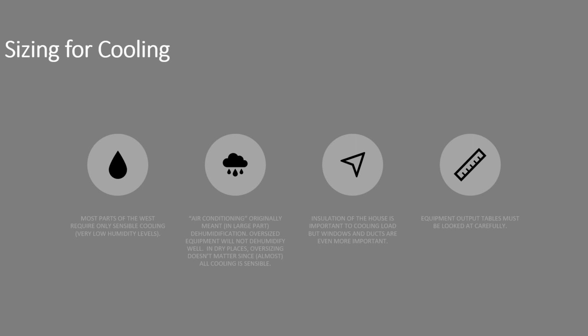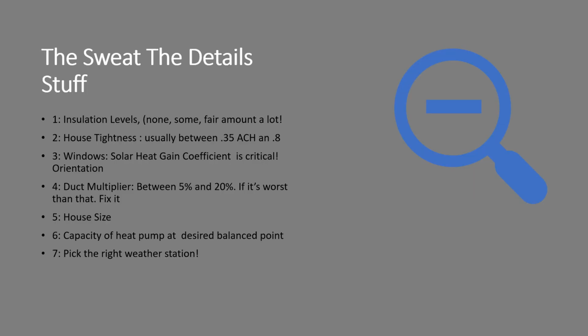And insulation of the house and good windows and good ductwork are probably the biggest factors that are going to influence the size of the heat pump that you put in. And I'm sorry, nobody likes to look at detailed capacity tables, but to pick the right system, especially for cooling, you really have to look at them. In summary, these are the items you sort of have to sweat the details a little bit on. Insulation levels, don't worry if it's an R33 or an R38. Doesn't matter that much, but none, some, or a fair amount sure matters in the ultimate size of the heat pump you put in the house.